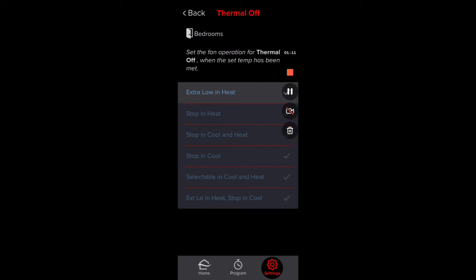Go into Thermal Off Fan and you have your choices. Extra Low in Heat is my preferred method whenever we install these units — I like the heat to be even, so you want the system running at a very low fan speed even though the heat has been satisfied. It just evens out the air.